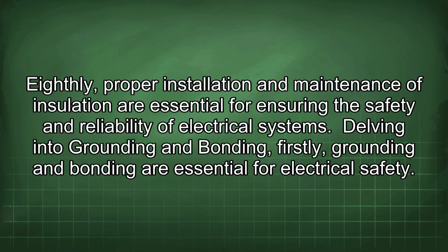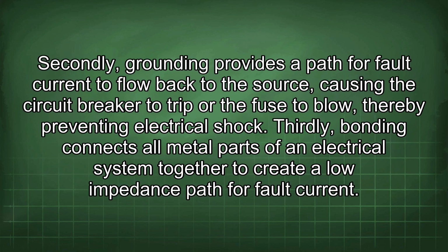Delving into grounding and bonding. Firstly, grounding and bonding are essential for electrical safety. Secondly, grounding provides a path for fault current to flow back to the source, causing the circuit breaker to trip or the fuse to blow, thereby preventing electrical shock.